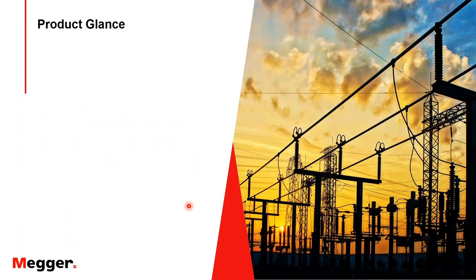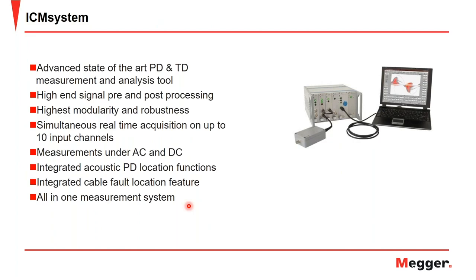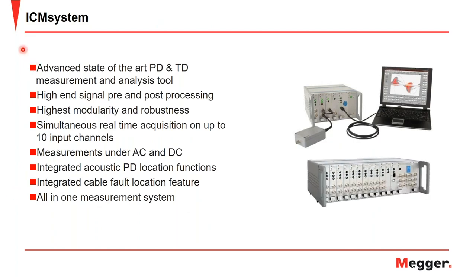So moving on, we got a brief glance at some of the products. Here we have the ICM system, which is our more advanced state-of-the-art partial discharge and tan delta measurement and analysis tool. It offers high-end signal pre and post processing, as well as the highest modularity and robustness available. It comes available with simultaneous real-time acquisition on up to 10 input channels and is capable of measurements under AC and DC. It does have integrated acoustic PD location functions, which we just covered, as well as integrated cable fault location features. And it's really seen as the all-in-one measurement system.